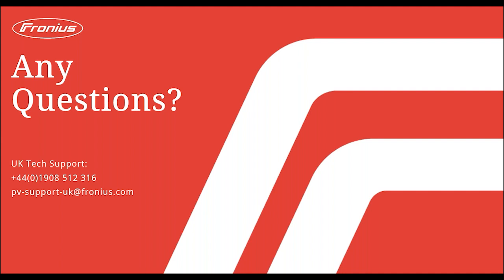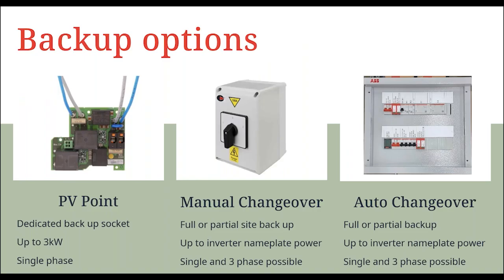Okay, thank you. Question from James, is the PV Point Comfort a hardware or software firmware update? So the PV Point Comfort will be a retrofittable board. It's a small circuit board which will fit into the AC connection area. So I can probably show that again on the screen. So it is this circuit board shown on your screen now, and that actually bolts into some pre-existing mounting points within the inverter and connects into the existing AC connections. So that is a new piece of hardware which is retrofittable to existing inverters.